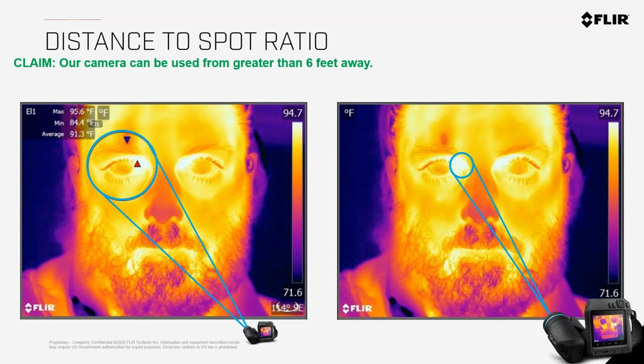Let's just use an example of 10 to 1. A 10 to 1 distance to spot ratio means that at 10 inches away, your thermal imaging camera will give you a target of 1 inch. It'll give you a temperature reading inside a 1 inch diameter. When you're 20 inches away, it's going to have a 2 inch diameter. If you're 10 feet away, you're going to have a 1-foot diameter as your target for that measurement.